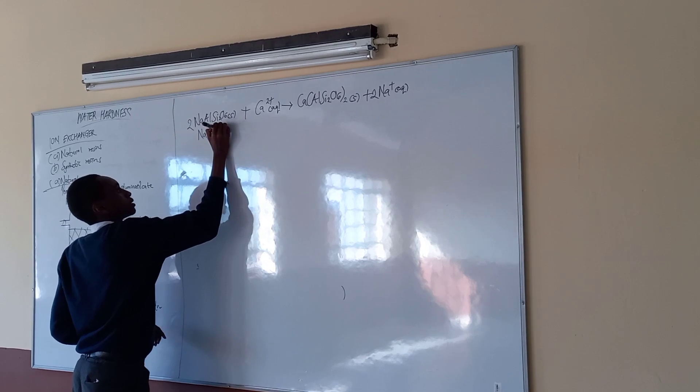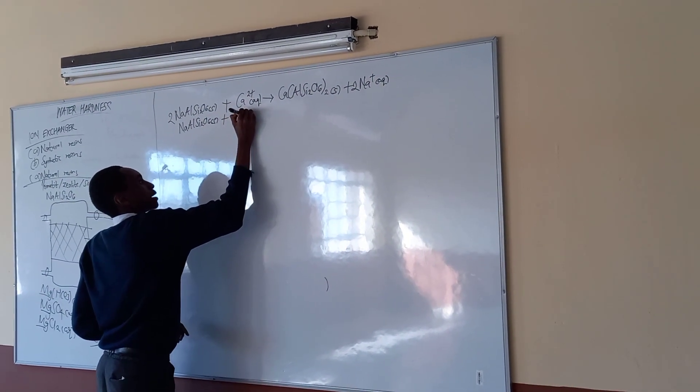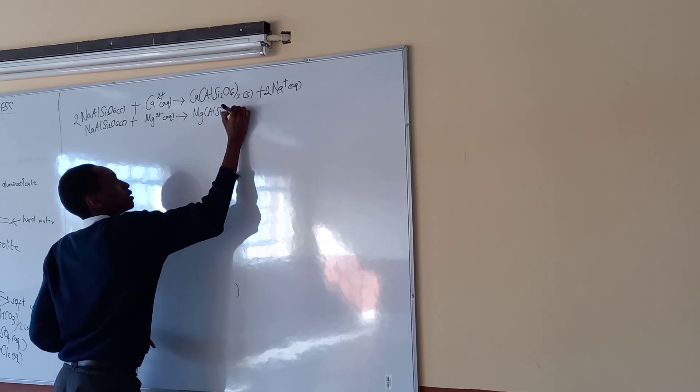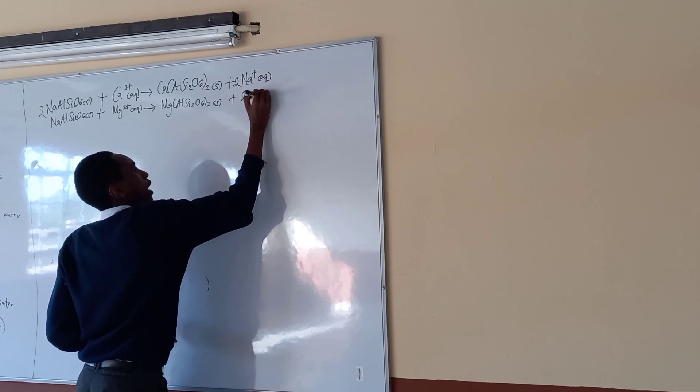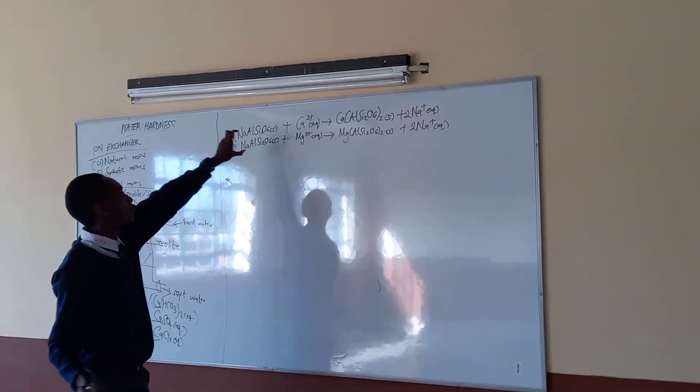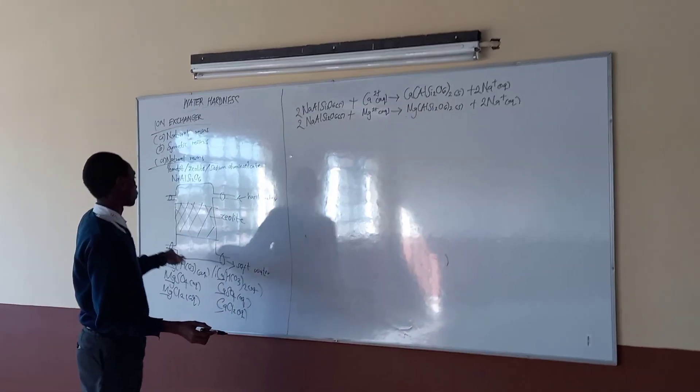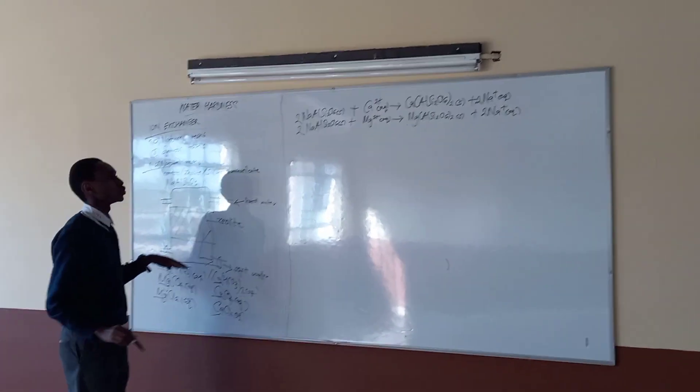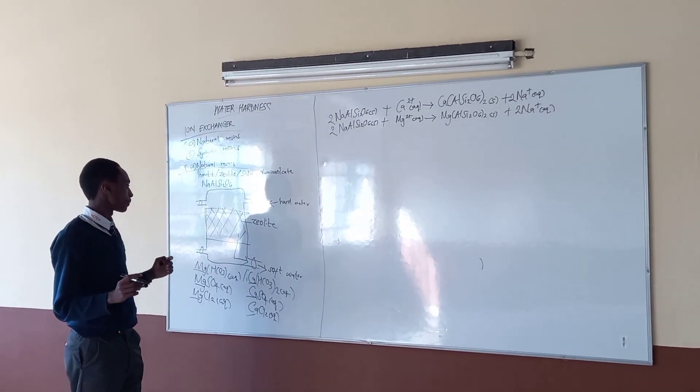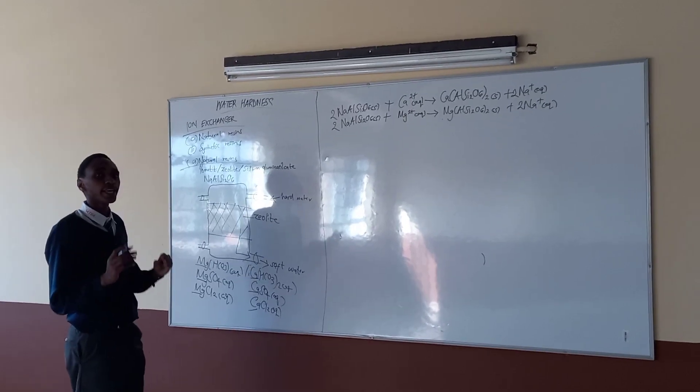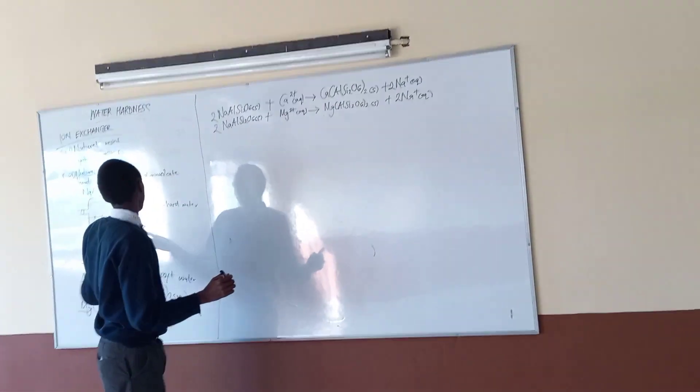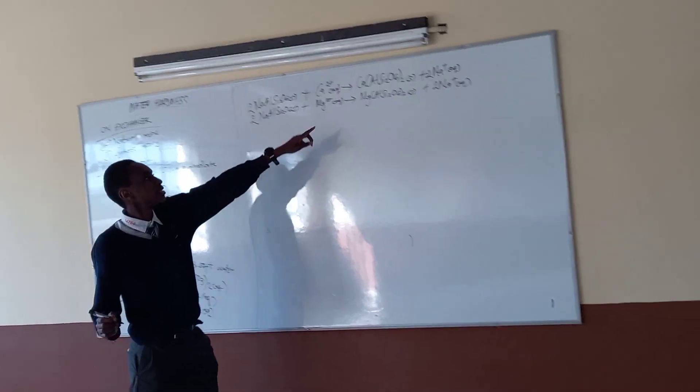Sodium aluminum silicate solid plus magnesium ions aqueous. We get to have magnesium aluminum silicate solid plus two sodium ions aqueous. Simply, that is how we do it. We get to remove the cation from the water. And the cation will remain in the tank while sodium ions will get to flow with the water. So as the water flows in this direction, it will be soft water. But what happens is, in the course of time, the zeolite is depleted. So how do we get to restore the zeolite?